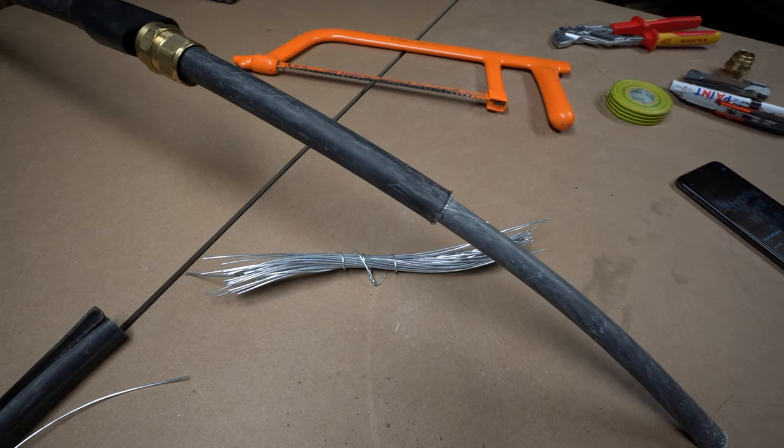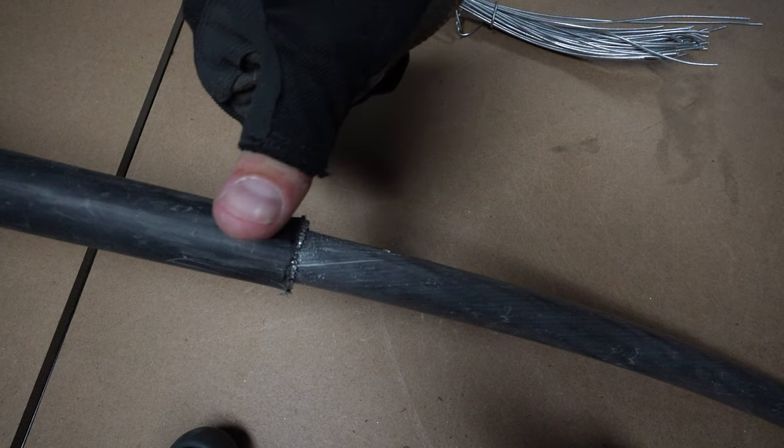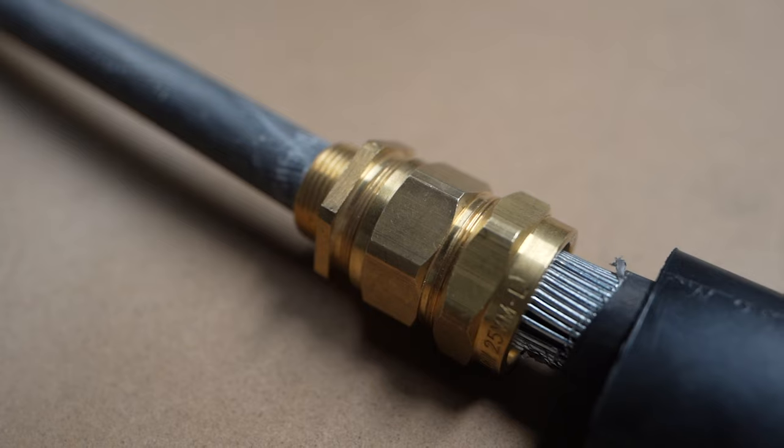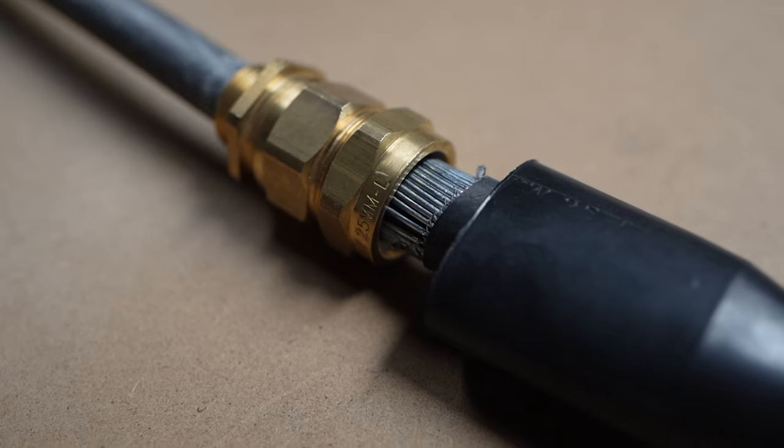You should now have the cable partly dismantled — inner sheath showing, then it stops where you've got the steel wire armoured and the outer sheath neatly cut ready for the gland. You then want to cut a little bit of the outer sheath off so the gland can be pinned between the steel wire armoured. How much you cut off is determined by the cable and gland size. With smaller cables — 10mm and below — a thumb's width is probably enough.